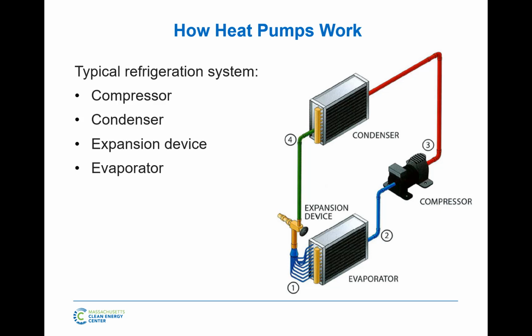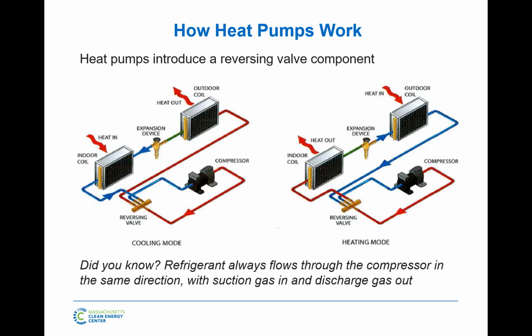The discharge line from the compressor to your condenser. Then you have your liquid line out to your expansion device. In residential mini splits, this device usually lives out in the condensing unit. In more commercial VRF, the expansion device usually lives in the multiple evaporators. Now, what is a heat pump?